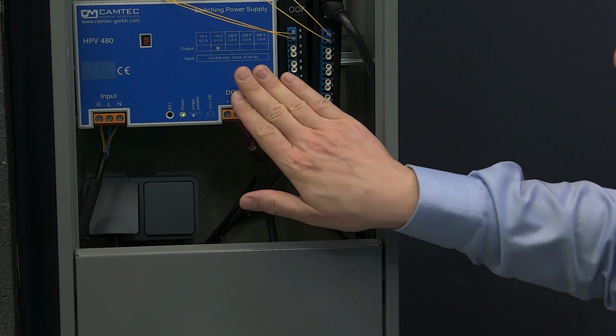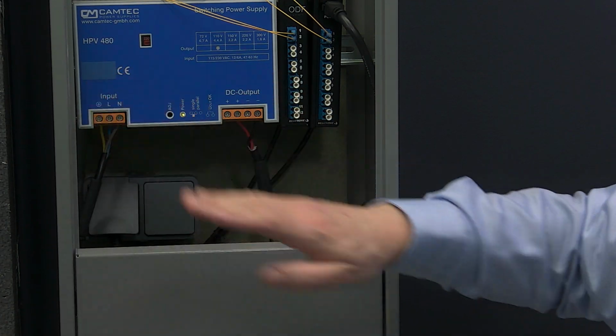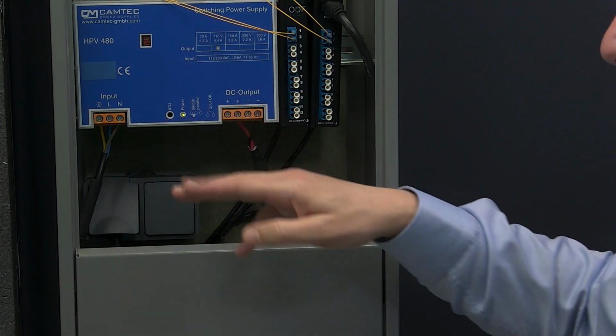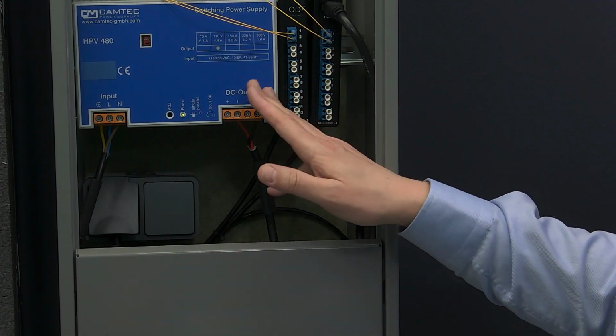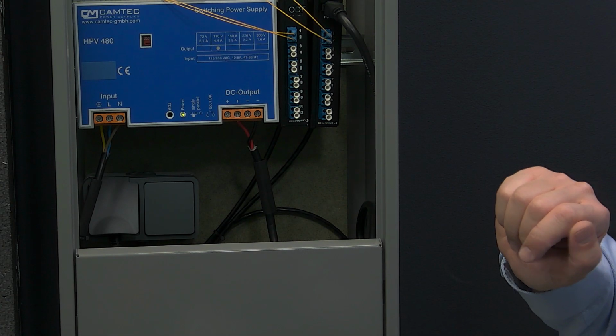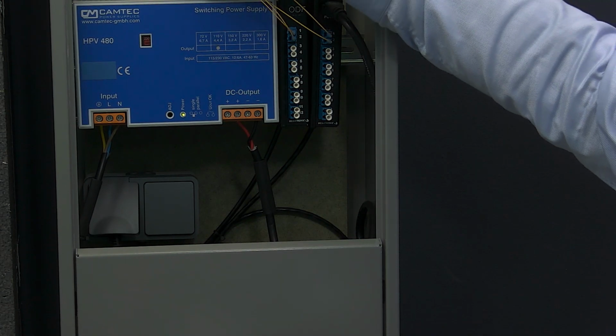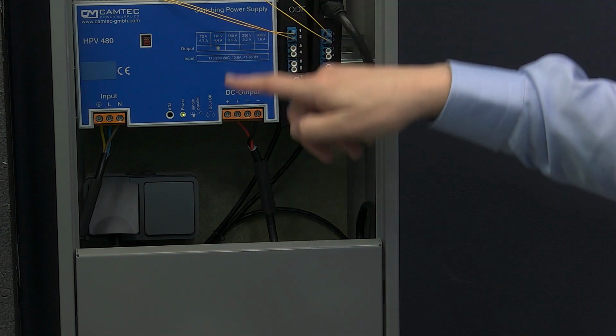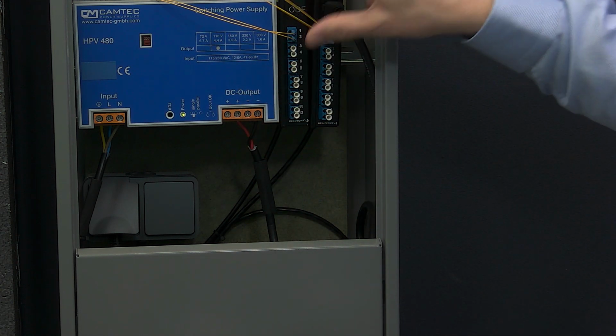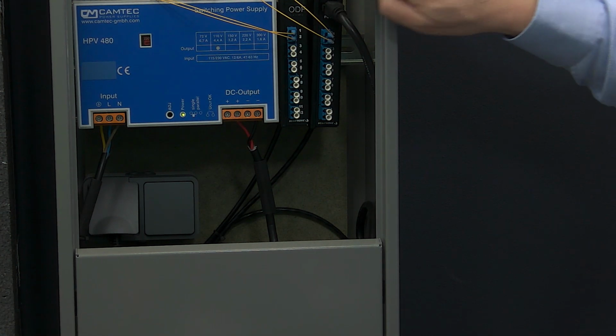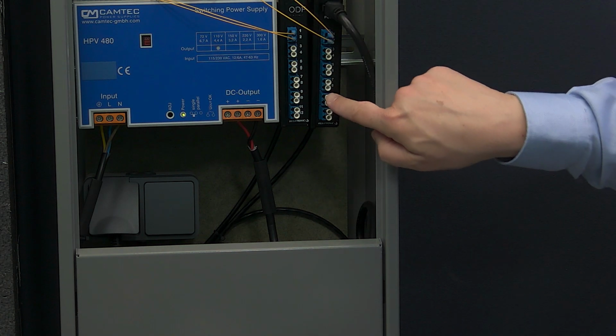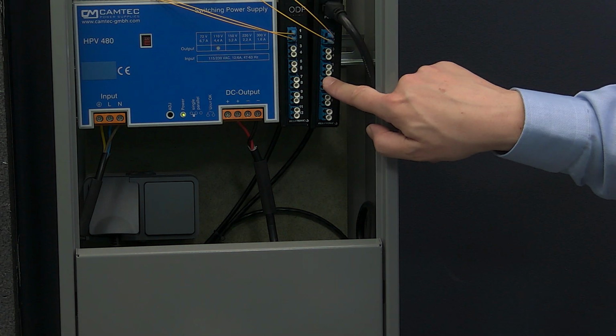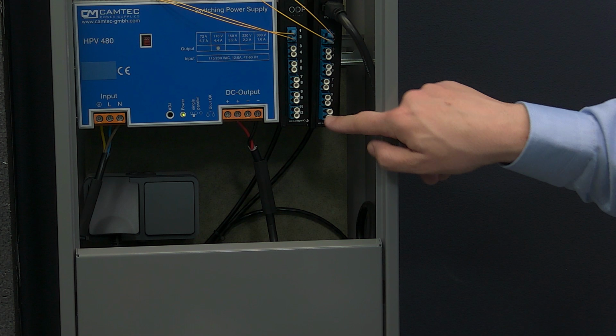Here we have an AC to DC rectifier, so we convert the AC power, typically 220 volts, to DC—as mentioned, 110 volts DC. Then here we're getting the fiber from our core network, and we bring in both the fiber and the DC power into this hybrid ODF here. Then we combine both the power and the fiber into the InOne cable.